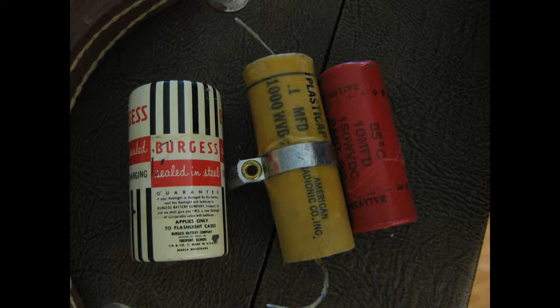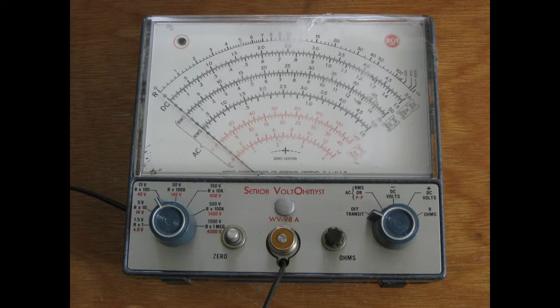I then followed the calibration procedure out of the manual. I first applied a DC voltage of 50 volts to the meter, and I tweaked the Cal plus potentiometer. Then you flip the polarity and you tweak the Cal DC minus potentiometer. I used a Variac to generate a 50 volt AC signal and did the same thing for the AC Cal potentiometer.